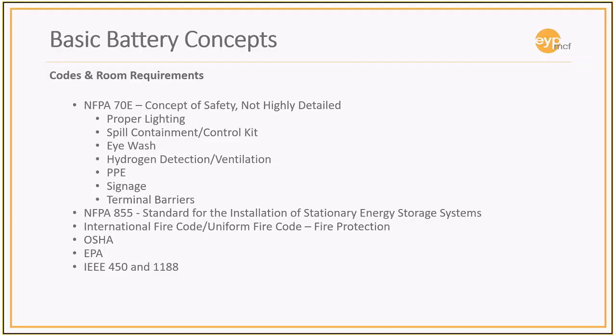So let's talk about code. In the old days, when everybody used flooded cell batteries, everybody was concerned about dropping a battery and getting sulfuric acid all over. There are spill containment requirements, eye wash requirements, the hydrogen detection that I spoke about, and the ventilation requirement during charge and discharge. There's certain PPE that you're required to have, and signage and terminal barriers.